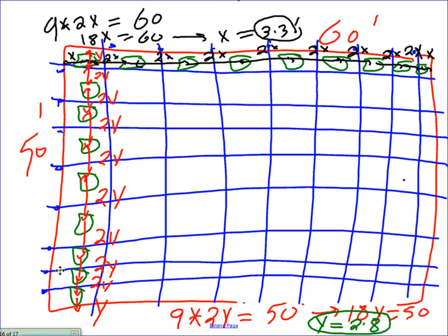And tomorrow, guys, you're going to be laying out the fixture for your friend Chad. You have all this diagram. I want to remind you, this side is 50, and this side is 60. How many columns am I going to have? I decided 9 by 9, so I'm going to have 9 columns and 9 rows. If you count, here's 1, 2, 3, 4, 5, 6, 7, 8, 9. The same thing, the rows are 9. In the center of every 9 by 9, you're going to have rectangles. At the center of every rectangle, you're going to have one fixture.